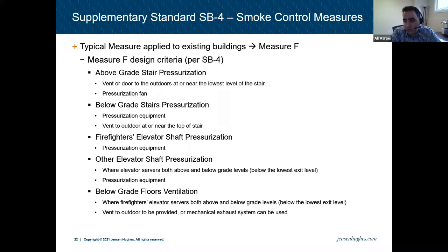And the other requirement is for the elevator shaft. So if you have a firefighter's elevator shaft, you need to pressurize that, basically with a fan pressurizing the shaft to keep it clean and clear of smoke. If you have other elevator shafts other than the firefighter's elevator shaft, when the elevator serves both above and below grade levels, the term is below the lowest exit level. The lowest exit level typically is your ground floor. And if that elevator serves below the ground floor, you need to pressurize that.